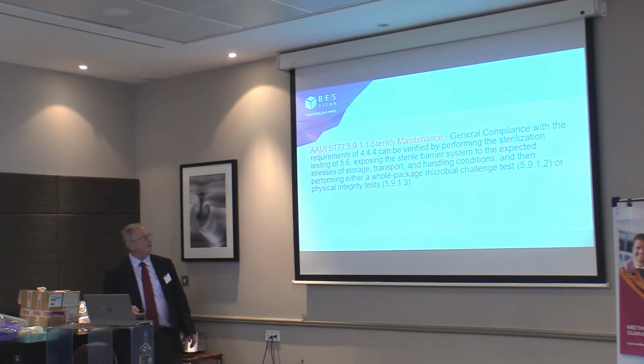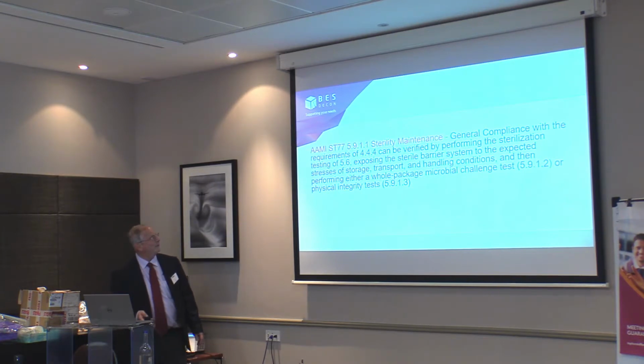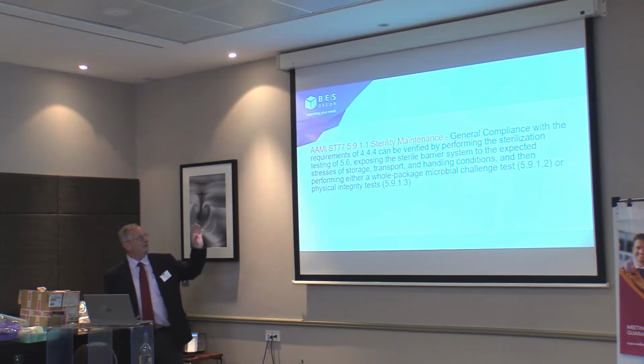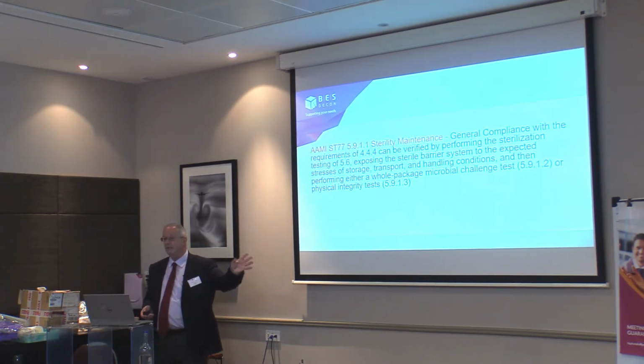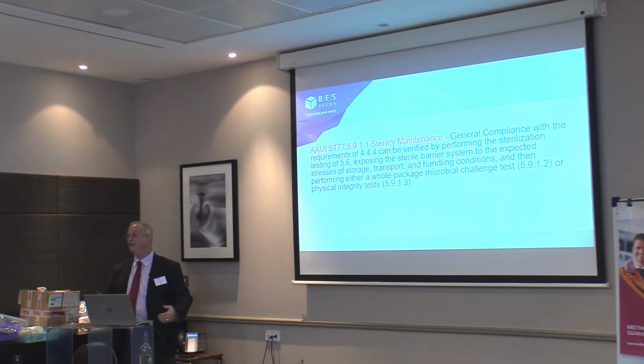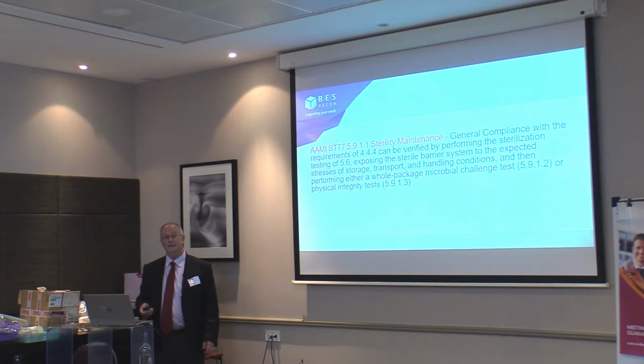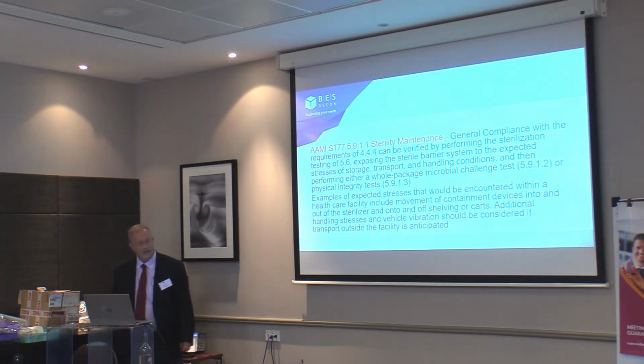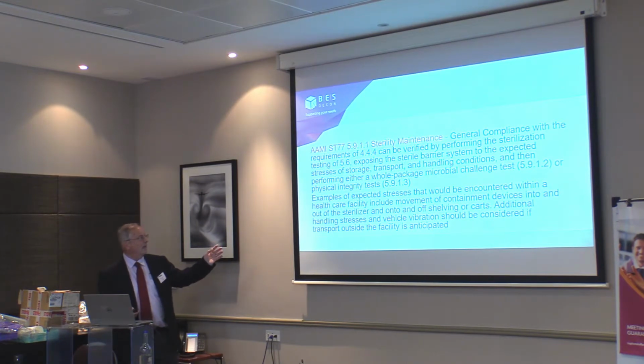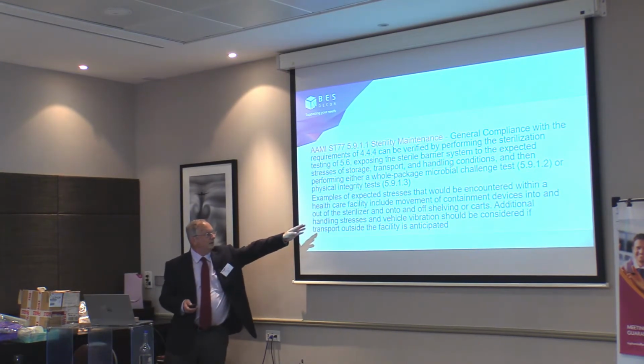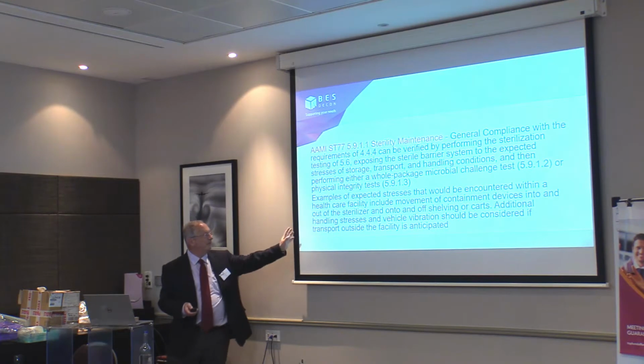And the definition of sterility maintenance is that you can verify it by performing the testing elsewhere in the standard, but you should be exposing the sterile barrier system to the expected stresses of storage, transport and handling conditions, and then performing either a whole package micro test or physical integrity tests. So those are all there in the standards. But it's saying, don't put it in a static situation, put it through what it's normally going to go through to see whether your barrier system is actually working. And examples of expected stresses deal with moving in and out of the sterilizer, on and off shelving, onto carts, and stresses from vehicle vibration as things are being moved around, and so forth.